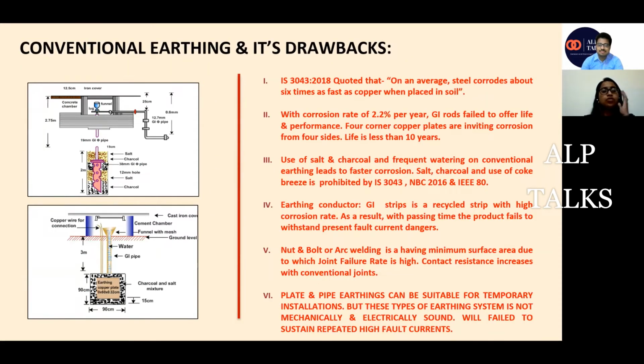Basically, if I tell you the drawbacks of conventional earthing, of pipe earthing or plate earthing: on average, steel corrodes 6 times as fast as copper when placed in soil. When we are talking about GI material, it is a zinc coating over the iron only, so it also corrodes very fast in the soil. That's why after 4 or 5 years the earthing starts having issues, because the pipe starts corroding and is damaged completely below the ground. And earthing is a thing that is out of sight, out of mind. So no one thinks, once it's installed, that it may have any issue.